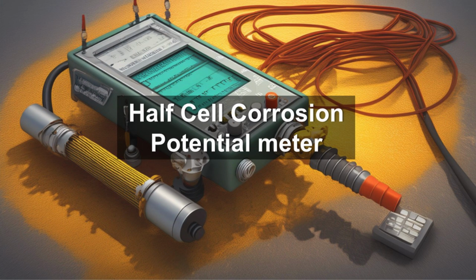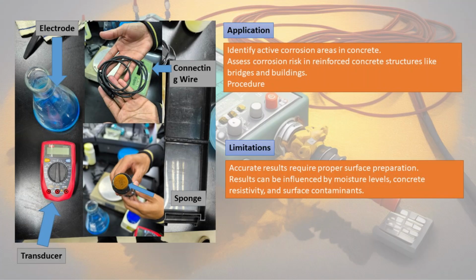Last is the half-cell corrosion potential meter test, a non-destructive method used to assess the risk of corrosion in reinforced concrete structures. The type of equipment used were a half-cell corrosion potential meter, which includes a reference electrode, typically copper-copper sulfate, a high-impedance voltmeter to measure potential differences, connection wires, and a sponge and gel to ensure proper electrical contact. The applications of this test helps to identify active corrosion areas in concrete, assess corrosion risk in reinforced concrete structures like bridges and buildings.